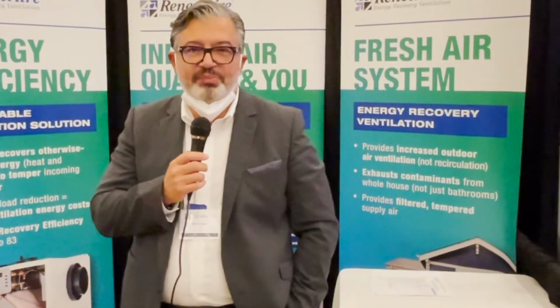We use a Generation 5 energy recovery core, and it offers up to 80% on the sensible side and 50% on the latent side, for a total of about 58% energy recovery.